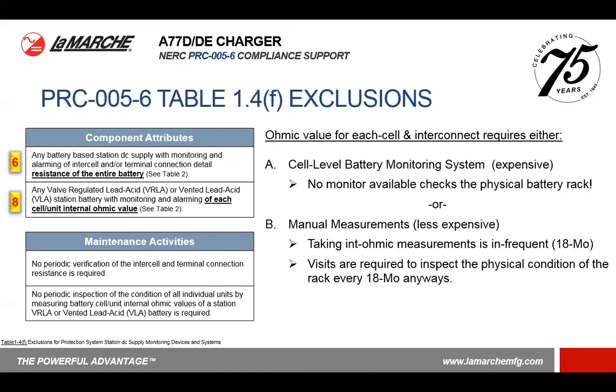Another option could be accomplished by taking manual measurements, which could be less expensive. Taking the internal ohmic measurements is pretty infrequent. It's really only required once every 18 months. And you have to be there at 18 months anyway to inspect the physical condition of the battery rack. So it makes sense for these particular points to accomplish this with manual measurements.